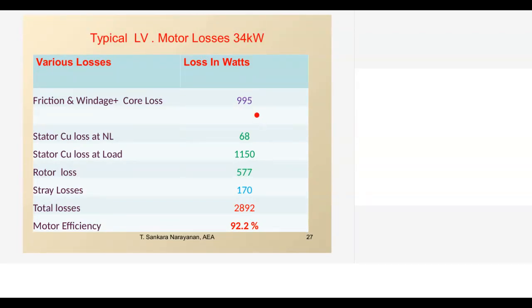See, I have put this figure mainly because many a time we refer that when rewinding is done, losses can increase. So when the motor goes for rewinding, which loss will increase? Anybody can type or answer. So when the rewinding is done in a motor, which loss will increase? You can answer. Rotor loss. Okay. Any other? Stator copper loss. Any other? So which losses will increase because of rewinding?